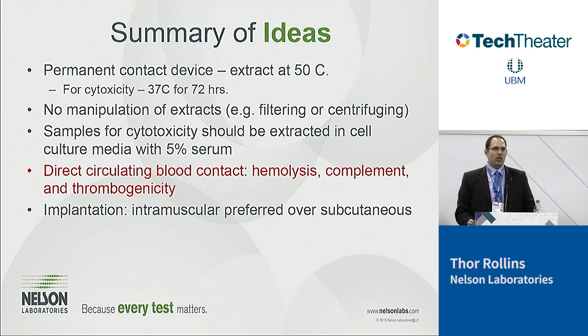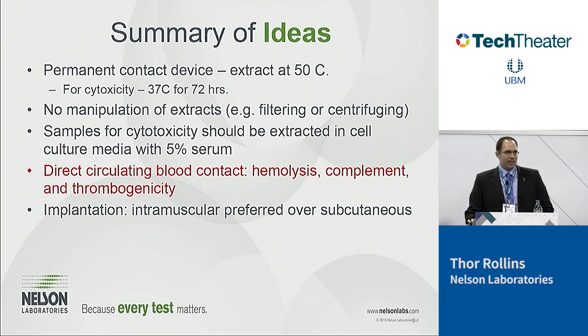This is one that did change for this new guidance document that we've seen the FDA start to ask for. And it has to do with cytotoxicity. For years, in fact, in the ISO standard today, it says do not extract for more than 24 hours at 37 degrees Celsius. Because, and I know I don't want to get too technical here, but the MEM fluid we extract in has L-glutamine in it. The L-glutamine degrades over time. So the thought is that we're making the test more sensitive the longer we extract it. So just do 24 hours.